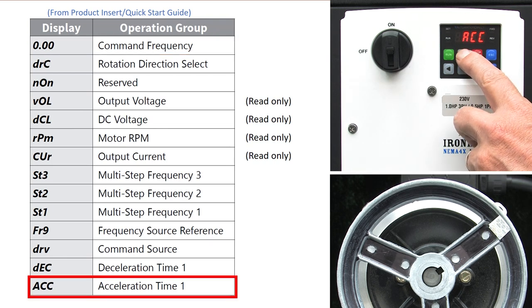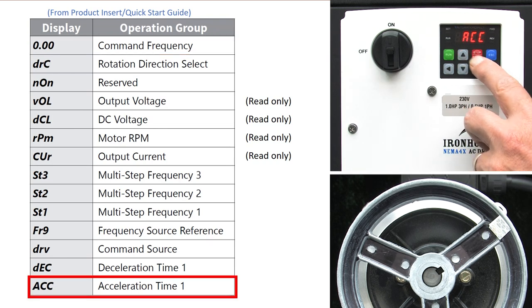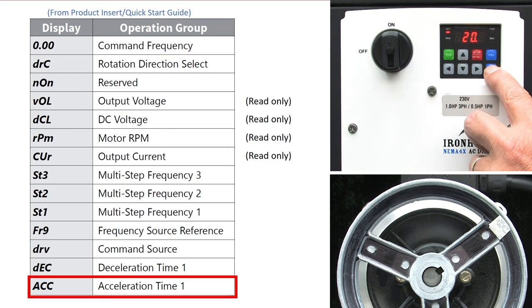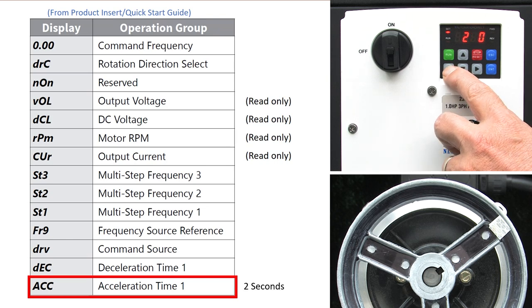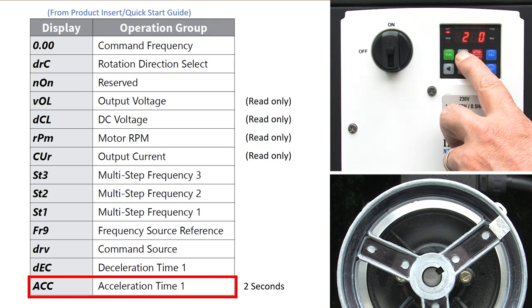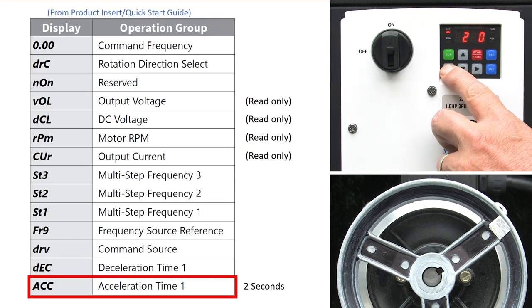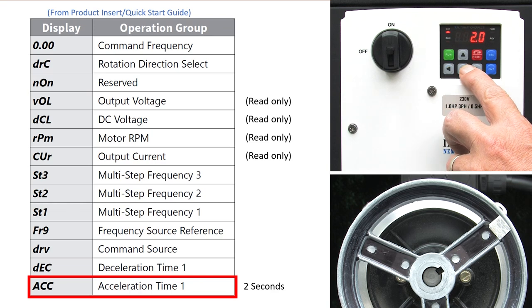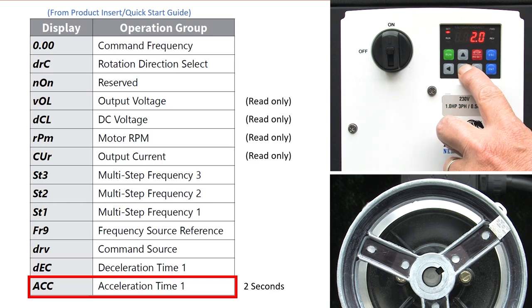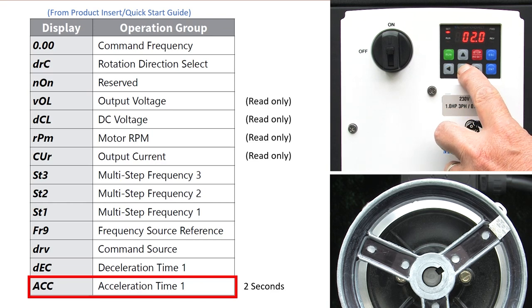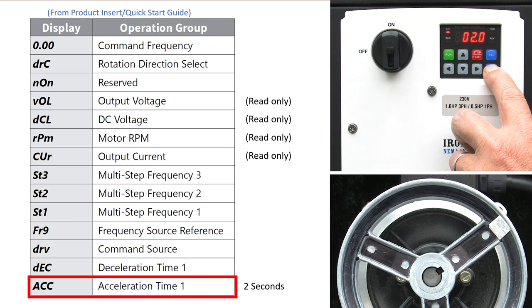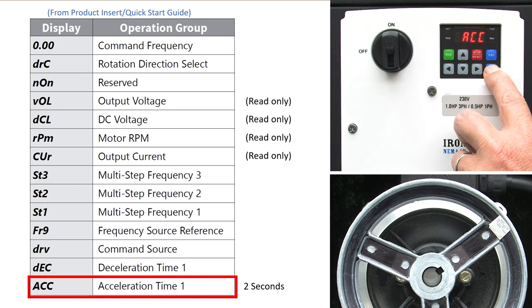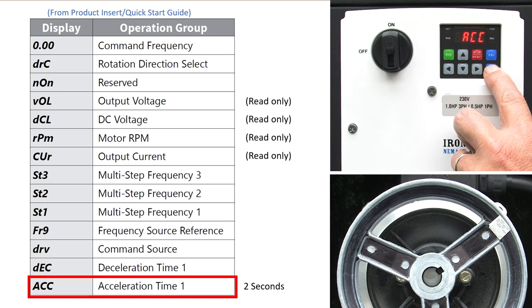I'll up arrow once and we get the acceleration parameter. Press enter to drop into that and we see it's a 20 second acceleration time. I'll scroll over to the ones digit, change it to a 2 and scroll over to the tens digit and change that to a zero. Press enter to select that and press enter again while it is blinking to accept it. And just like before, if it stops blinking you will have to press enter twice.